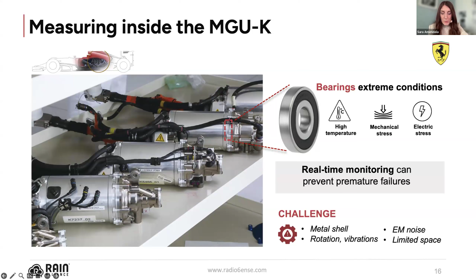RAIN sensors are promising to overcome the limitations of wired sensors and also of infrared solutions that require a clear line of sight with the point of measurement, which cannot be guaranteed in this case. However, we need to consider that bearings are inside a closed metal cavity with a lot of space constraints. The components are rotating, vibrating, and we are inside an electrical motor, so we should expect also some issues in terms of noise and interference.